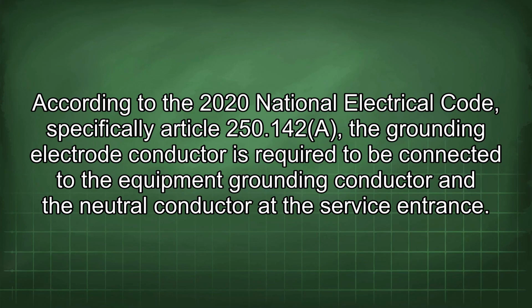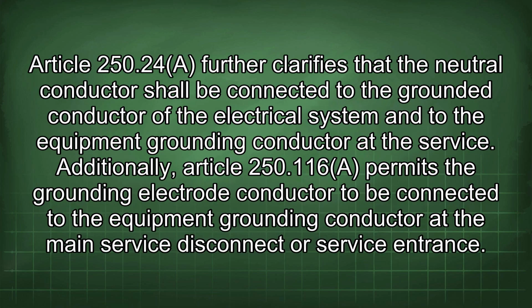According to the 2020 National Electrical Code, specifically Article 250.142(A), the grounding electrode conductor is required to be connected to the equipment grounding conductor and the neutral conductor at the service entrance. Article 250.24 further clarifies that the neutral conductor shall be connected to the grounded conductor of the electrical system and to the equipment grounding conductor at the service.